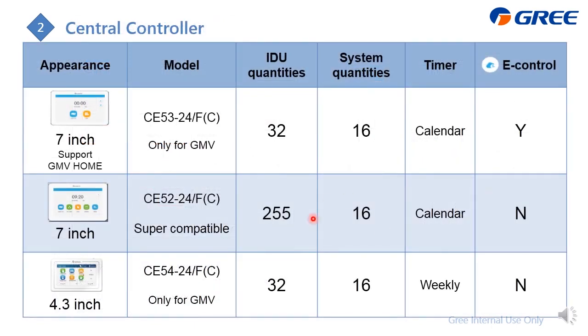As for the central controller, this is the summary of it. Currently, we have these three types of the wire controller, which are the CE53, CE52, and CE54. First is the size. The first two are 7-inch, and the last one is 4.3. This one can support GMV Home, and also you have the e-control. E-control means you can preset your appointed indoor units in your appointed operating mode or operating setting. Then when you activate this e-control, your appointed indoor units can operate in your operating mode to avoid setting them one by one. And also the connectable indoor units are a little bit different. Just pay attention here.